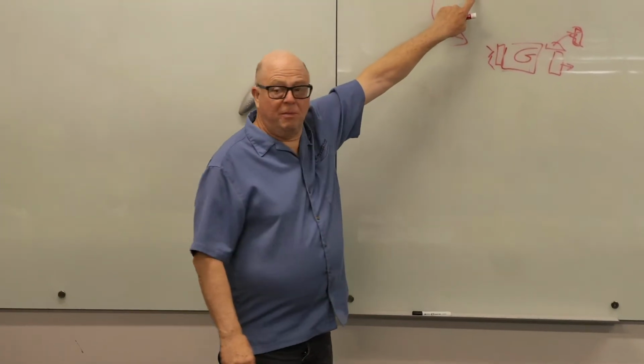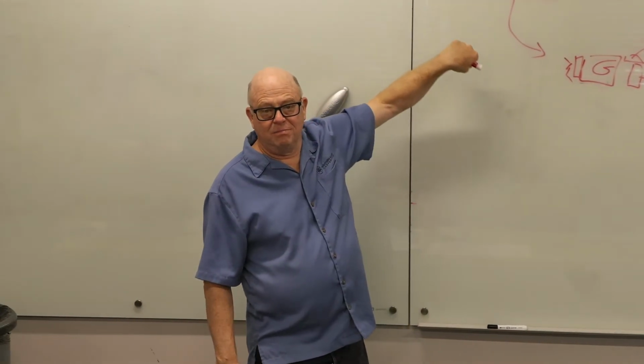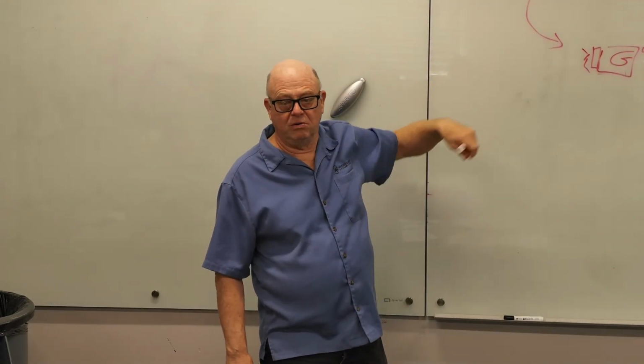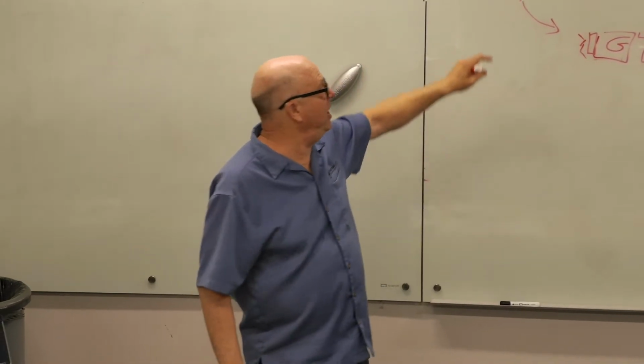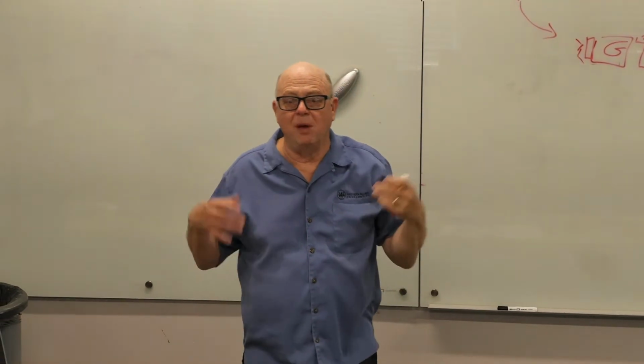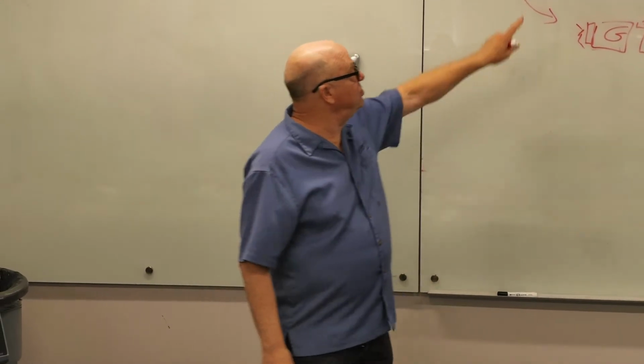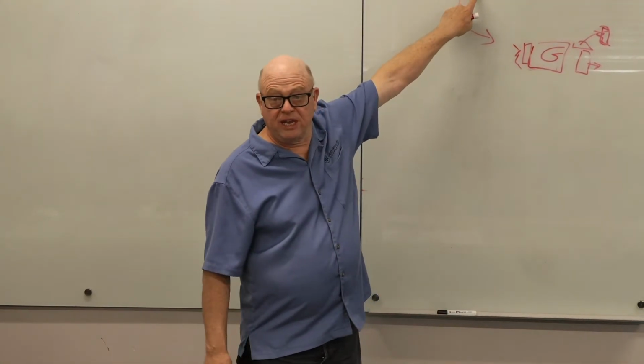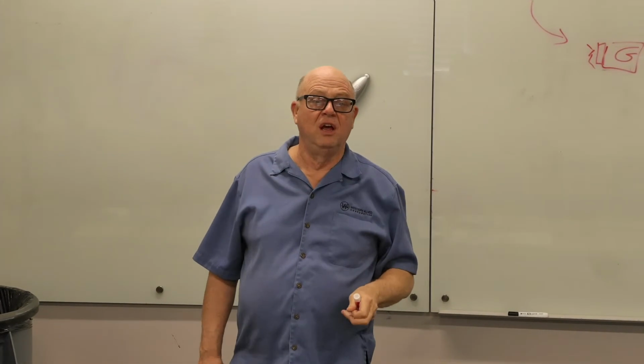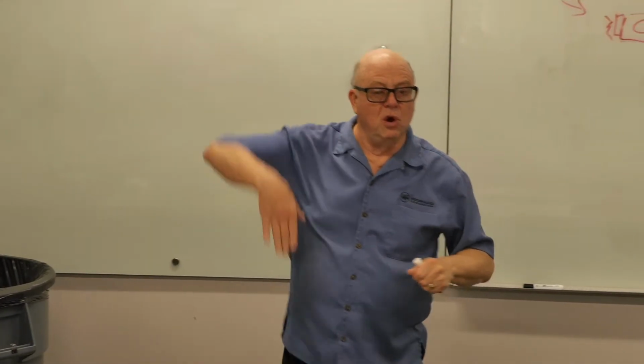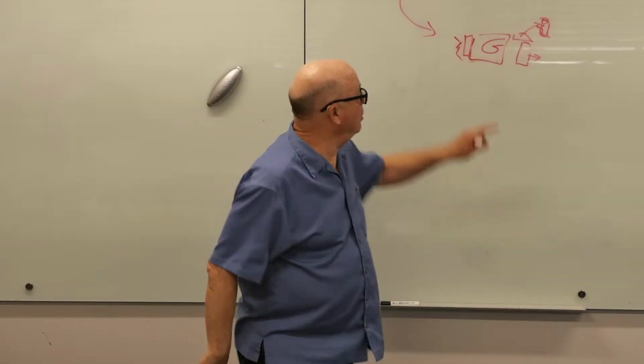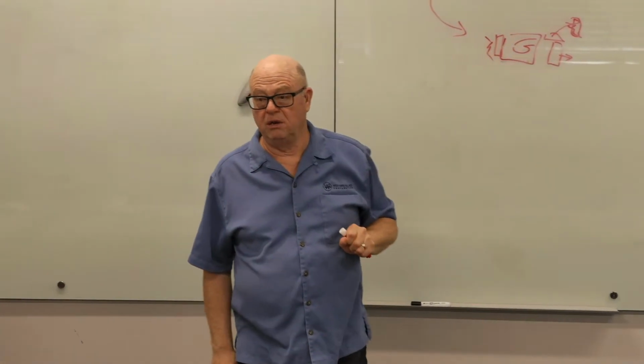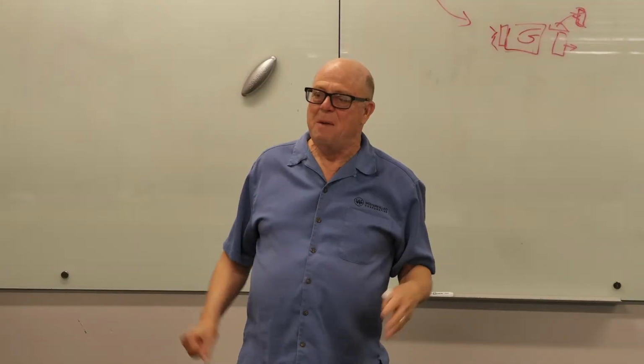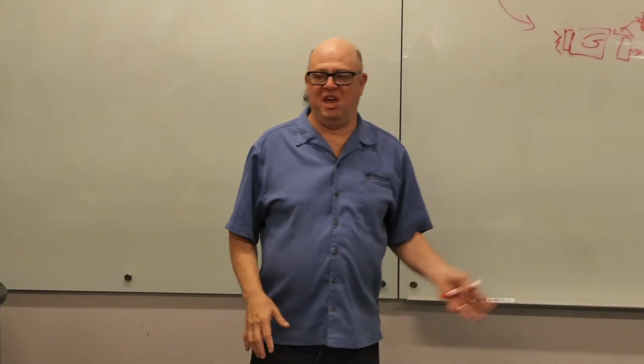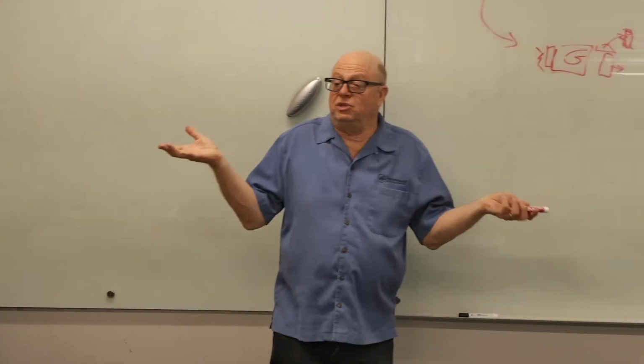So if you're trying to get so much outside air to meet some medical surgery standard or for a clean room, because they often have separate fans, or some application where you actually care about the amount of outside air you get, and you're using an ECM motor in the little guy, the chances of it being able to go off and on without coordinating with this going off and on are about 0. Okay? Because they are so weak, and we didn't know that. So then the question is, what do you do about that?